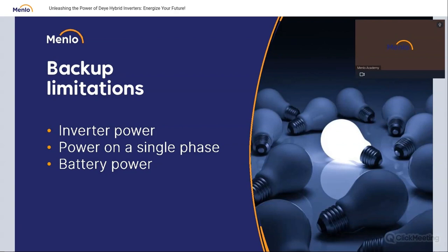Power on a single phase. What does it mean? Each inverter has limitation not only from overall installation or overall loads, but also has some limitation for a single phase. So if you have limitation of 33% and you have a 10 kilowatt inverter, you cannot put more than 3.3 kilowatts on one phase.